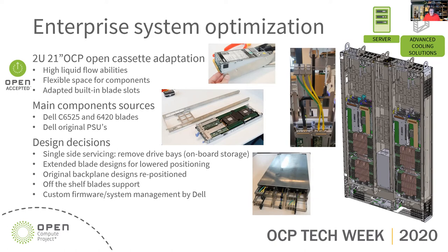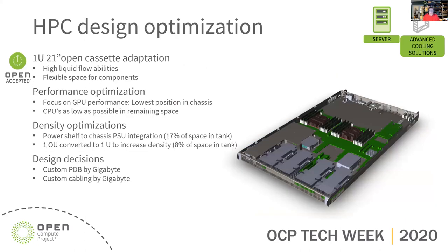The blades become serviceable from the top side, but since the top of the liquid is also the hottest part of the environment, we need these blades to extend all the way to the bottom of the tank. All the blades are extended with adapters, and this also accounts for the power supply. In this situation, all CPUs and power supplies are in the lowest parts of the immersion tank, receiving the coolest liquid first — important for reliability. You still maintain a dual power supply and serviceability; the only sacrifice is no hard drive bay, so this configuration relies on onboard storage.